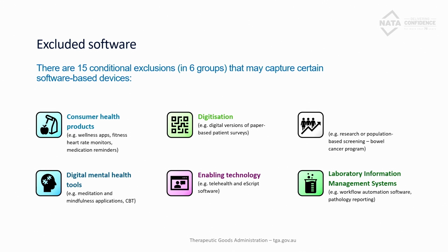So LIMS that enable laboratories to automate workflows, manage orders, samples, associated information. So where they don't include functions of diagnosis, so they can present the information and the outputs of your laboratory testing. As soon as they're making diagnostic or treatment suggestions, they're actually being pulled back into the regulatory framework.